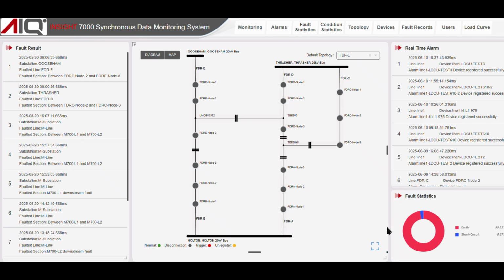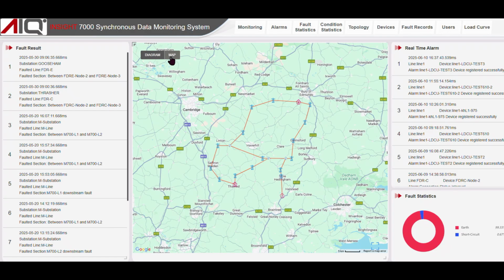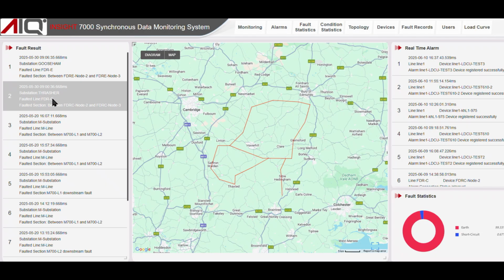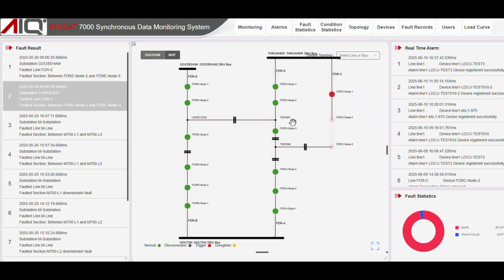It consists of 3 substations and 5 feeders that are all interconnected by tie switches which are open. The positions of the substations, Thrasher, Gooseham and Holton, together with their feeders and nodes, can all be shown on the Google map. Let us examine one of the simulated faults, which is fault 2 on the feeder C from substation Thrasher, which is an isolated neutral treatment. The fault was between nodes 2 and 3, and this is clearly shown on the Google map with the flashing faulted section. By clicking the network button, the faulted section is also flashing in the network diagram.